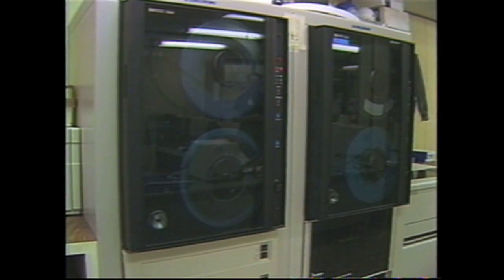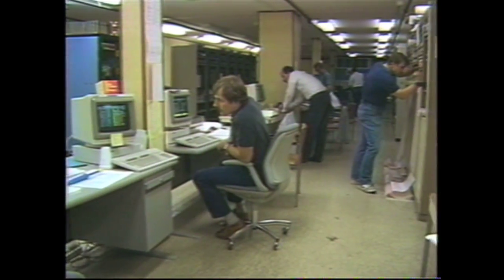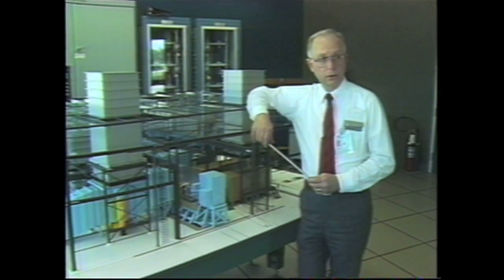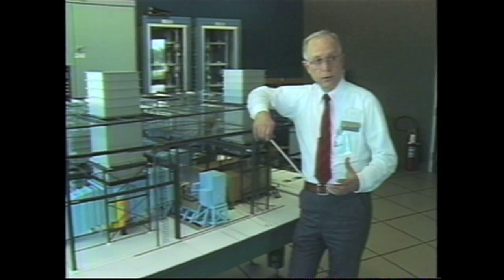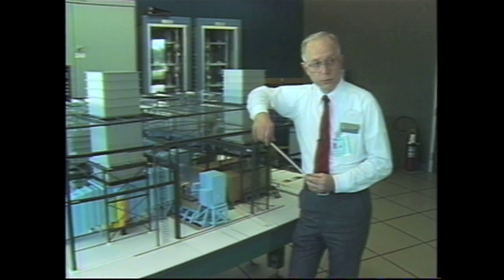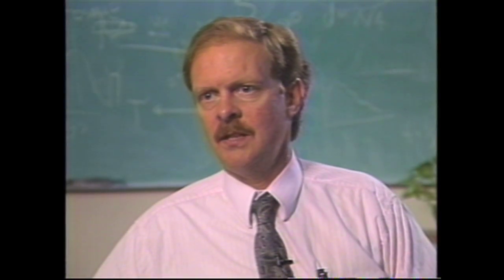There are over 100 of such displays that our engineers can call up here in Greenville as well as in Schenectady, New York, in order to determine just what is going on in this machine during a test in real time. We have completed all of our performance testing as well as our combustion and emissions testing, and I'm pleased to report that all of our engineering expectations have been fulfilled in this test. We didn't expect any surprises because we had fully tested the components and we didn't get any. We really expect from the data accumulated to date that this gas turbine is going to meet all of our expectations and then some.